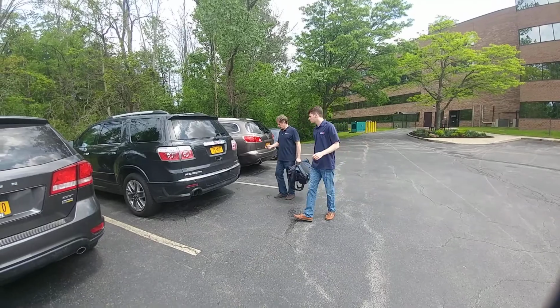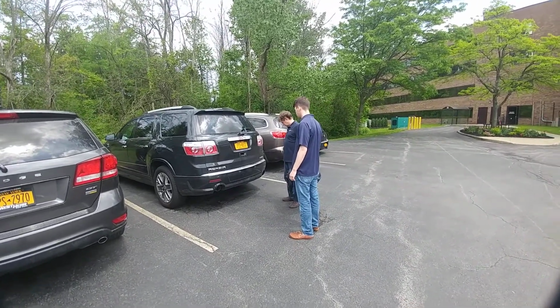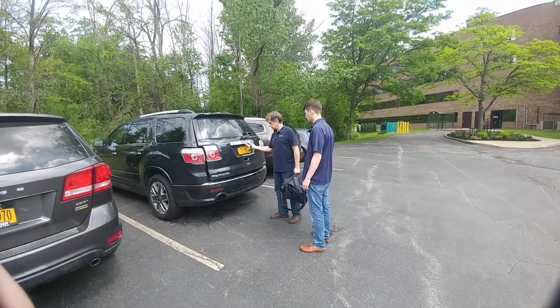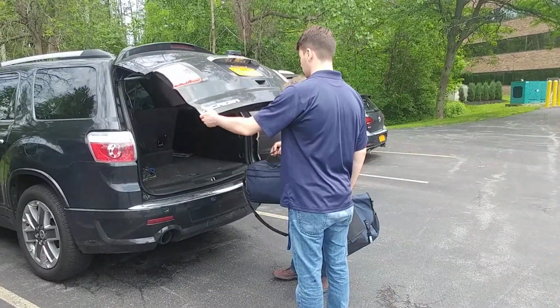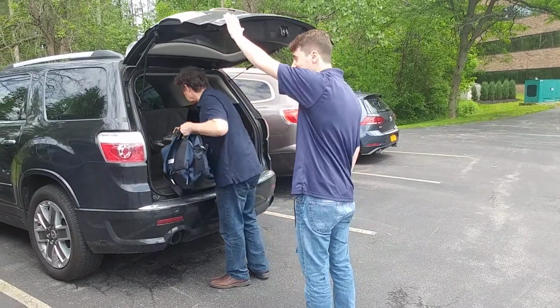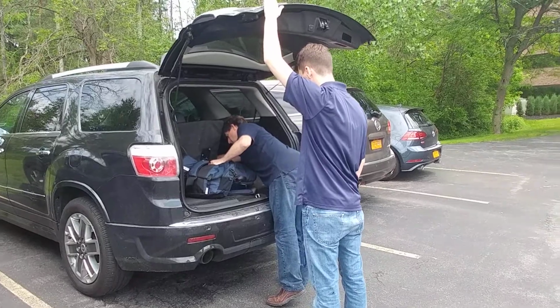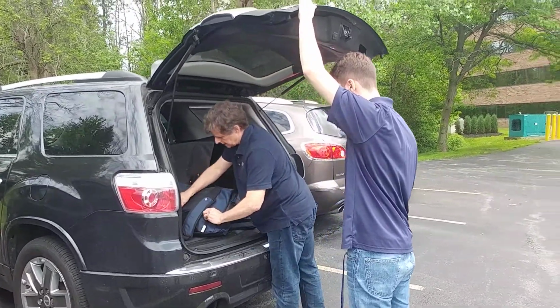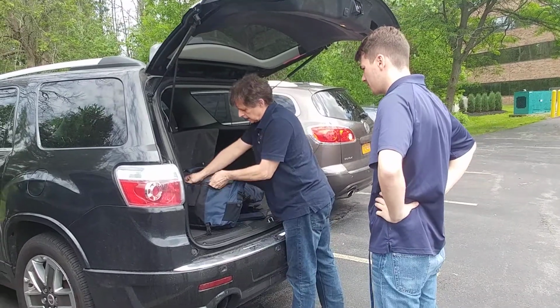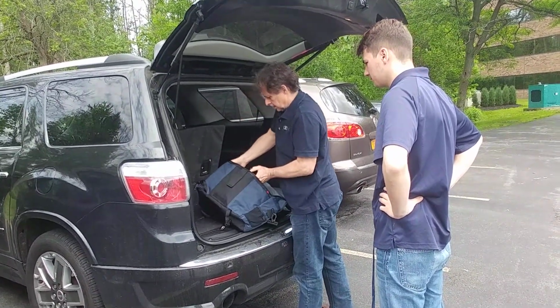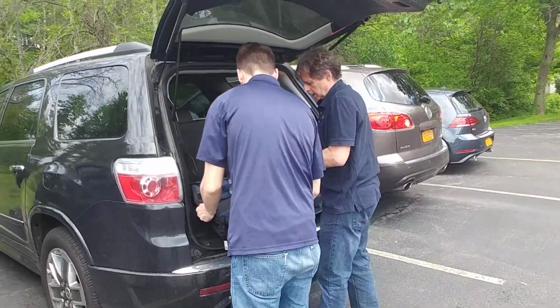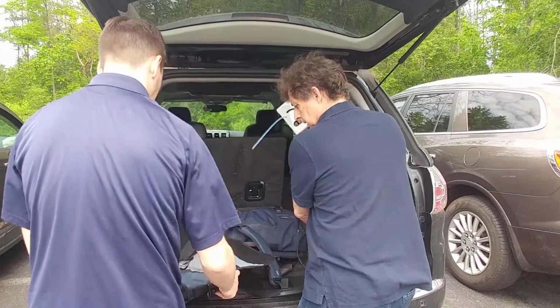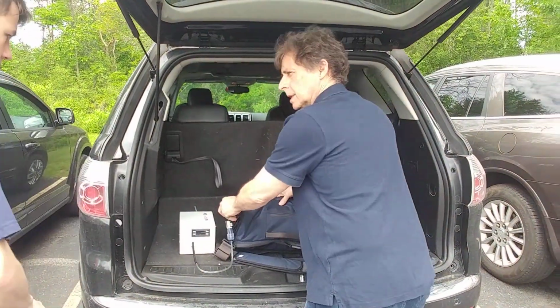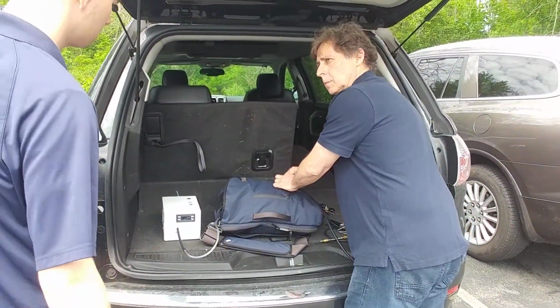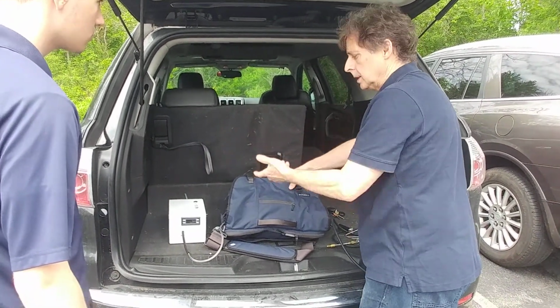Okay, test the Acadia. Okay, so what we'll do is get out the chiller. Actually, this is a condensate unit that works to take out excess water that will condense in the line. We have to protect the sensors from getting moisture in the optics, especially the optics and the electrochemical sensors.